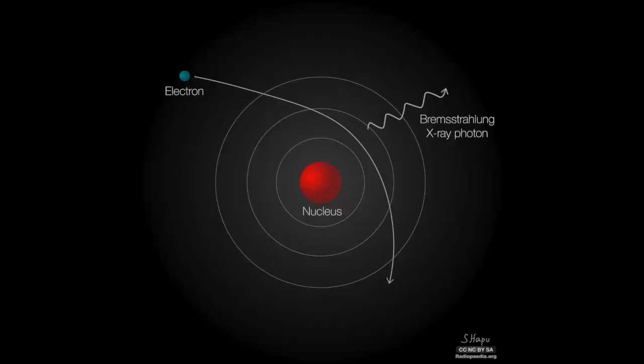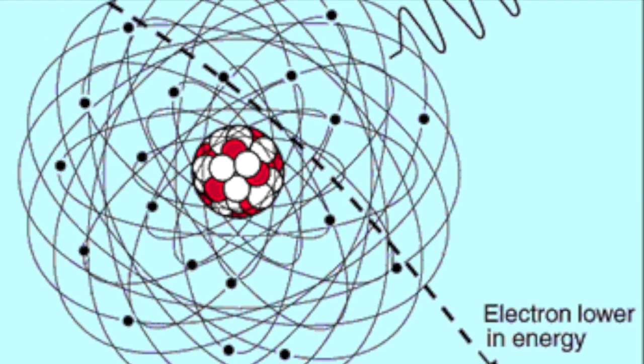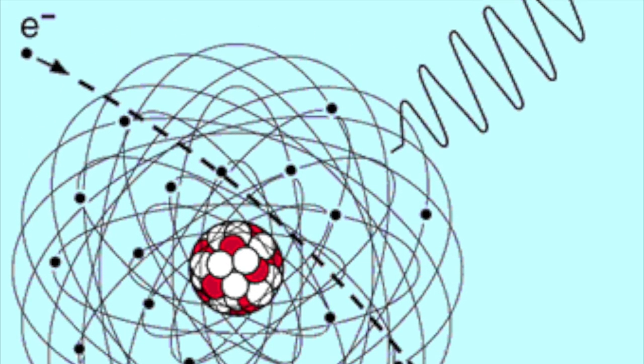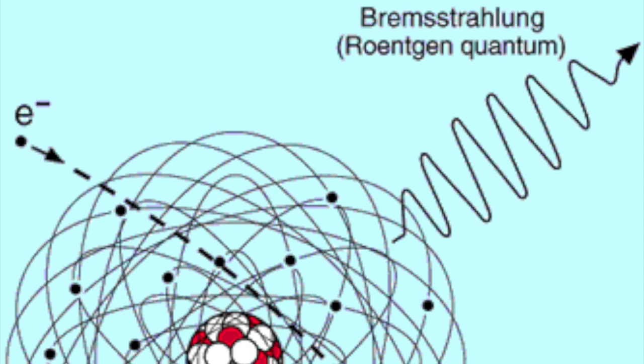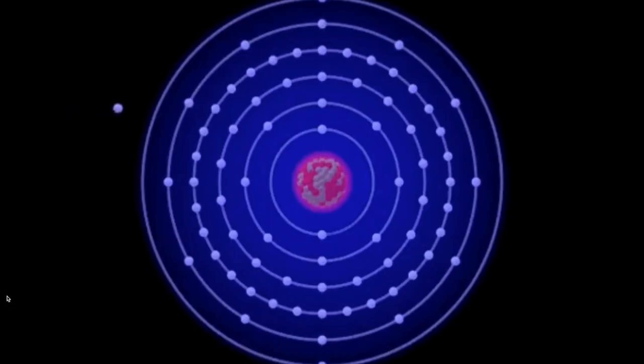A tungsten atom has a positively charged nucleus because of its protons, and it's surrounded by negatively charged electrons. All of these charged particles have an electric field that radiates around them. When electrons from the cathode enter the anode, some electrons are attracted to the positive charge of the nucleus within these tungsten atoms. As this happens, the electrons slow down or brake, and they also change direction. That lost energy is released in the form of an X-ray photon.